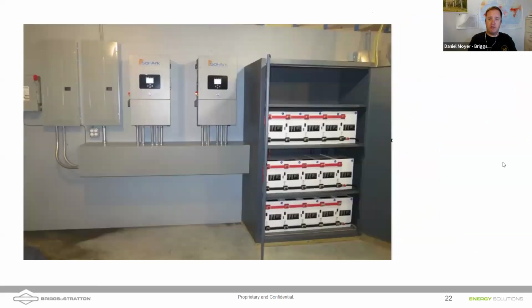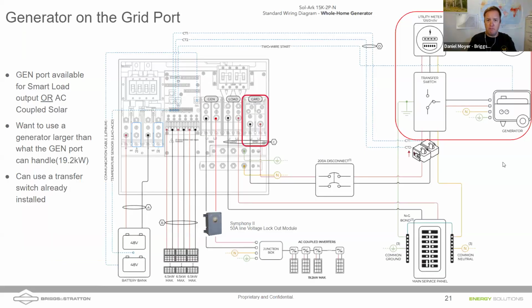Lastly, I want to make sure we talk through the rest of that slide. We've got about 20 minutes left, but let's cover what's going to happen when the grid comes back on. So say the power outage is over and the grid comes back on - the transfer switch will recognize the return of utility and transfer back automatically. That's incorporated in our Symphony transfer switch, and then essentially you're going to be running back like you normally would before.